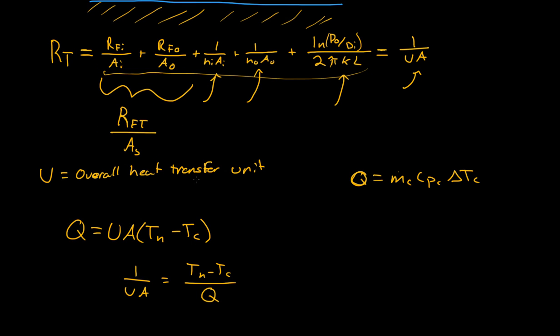The only thing I would add is usually this becomes Q equals UA delta T log mean - log mean temperature difference. Instead of using TH minus TC, you use a log mean temperature difference, and that will actually give you a better UA, or just a better U, because you know what this A is.